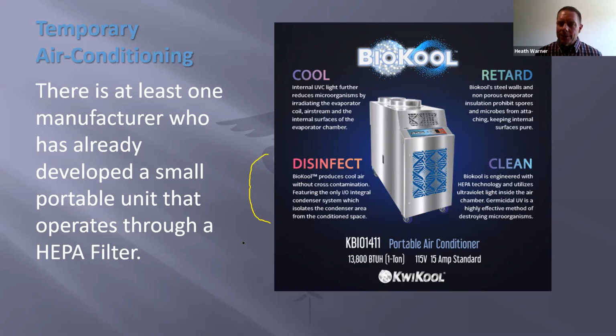For temporary construction use, I don't think it's probably going to become that valuable for our end of the industry. And it's specifically on that because it's designed for air volume and how long it has to hold that technology. And in all honesty, when you can get 99.999% filtration of all biologicals through a HEPA filter, there's really no reason to mess around with a UV light, because they're going to be temperamental and a lot more likely to be damaged under normal construction traffic. So stay tuned. We'll see where it develops, but it really is interesting to see people adapting all of their equipment to HEPA filtration this quickly.